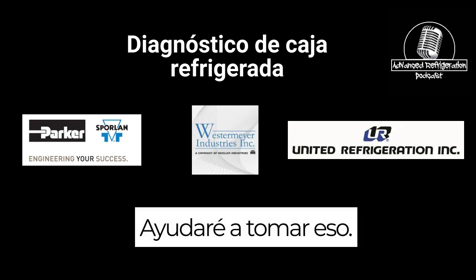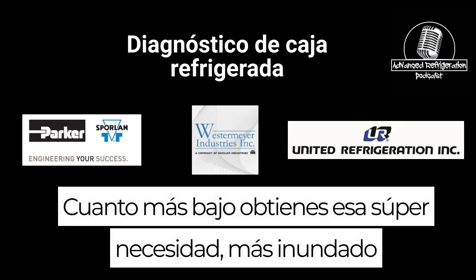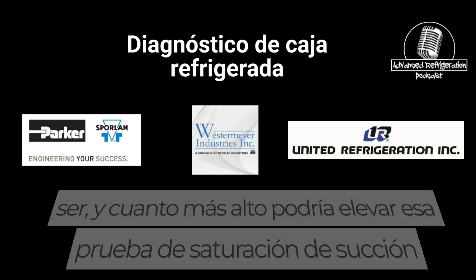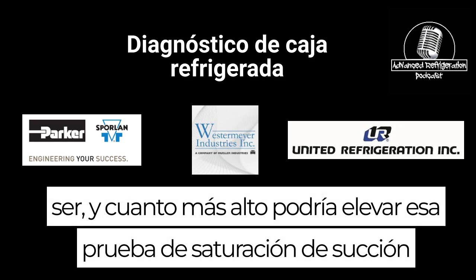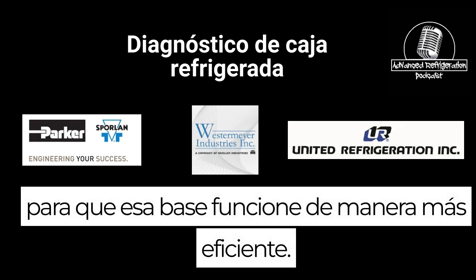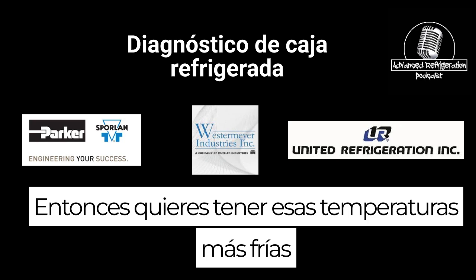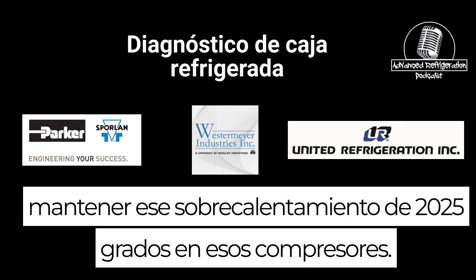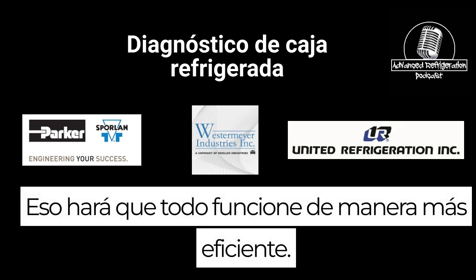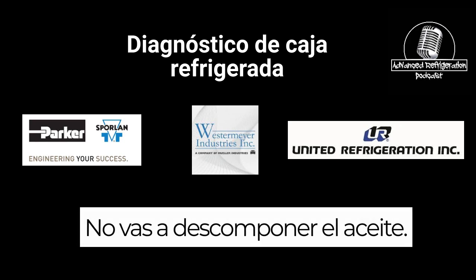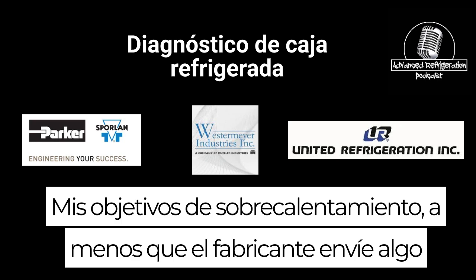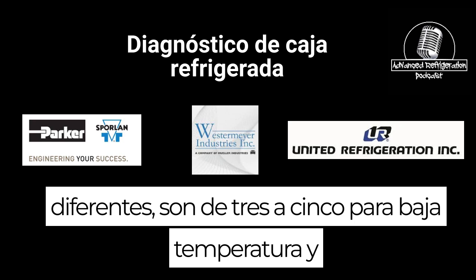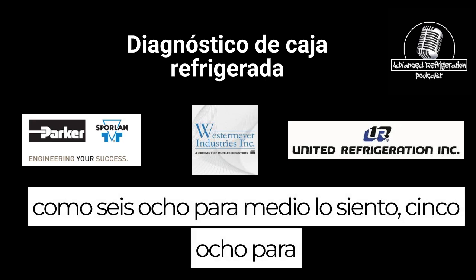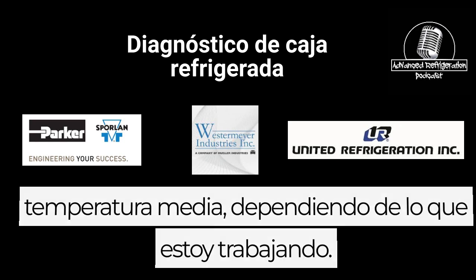I'll take that. The lower you get that superheat, the more flooded out that coil is, the more efficient that coil is going to be, and the higher you can raise that suction saturation temp to get that case to run more efficiently. You want those colder temps coming back to the rack so you can maintain that 20 to 30 degrees of superheat at those compressors, because that's going to make everything run more efficiently, and you're not going to break down oil. But my targets for superheat, unless the manufacturer sends something different, are 3 to 5 for low temp and 5 to 8 for medium temp, depending on what I'm working on.